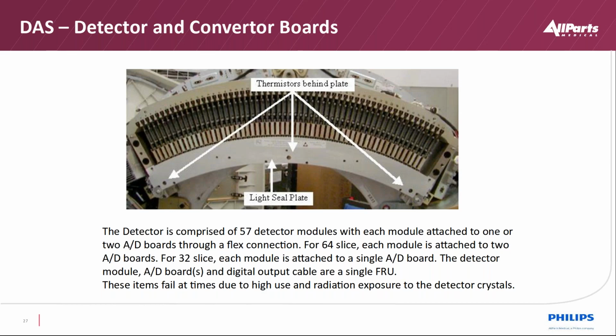So we have quite a few analog to digital conversions happening. This is sampled, one trigger will sample all the data from this detector, and we're doing that 936 times per gantry rotation. So a lot of data is being moved. That's why fiber optics are being used a lot to move the data from the gantry into the recon subsystem. And that's why the volume of data is very large.